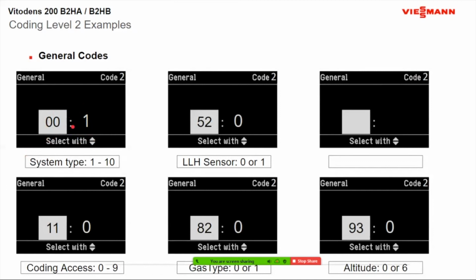If you look at our chart, and I'm pretty sure I'll have that come up here in a second, 00 is what type of system. On this one, I know I have one high temp system, and that's all I have on this boiler. If I had a 2 here, I would have one high temp system with domestic. As soon as you plug your low loss header sensor in, that would automatically change. But say you put it in and you don't want it in there, you would have to come into general here and make sure you put 52 to a 0.